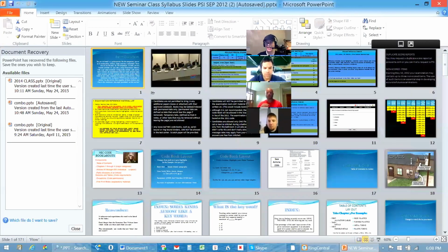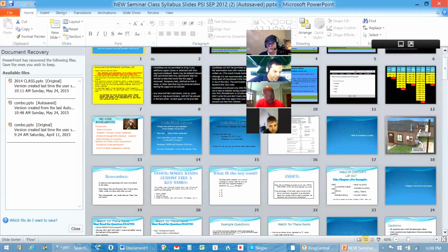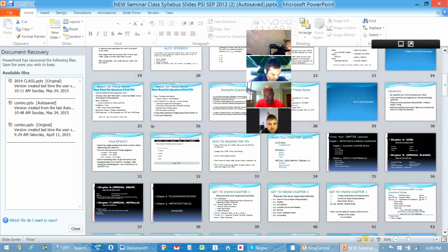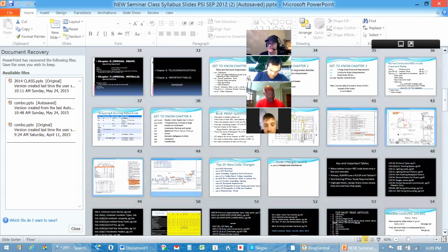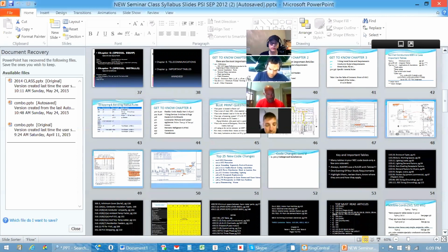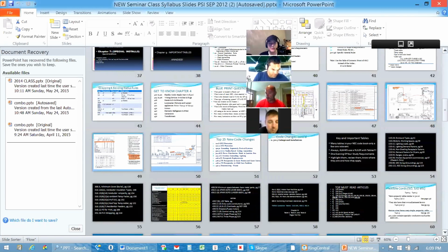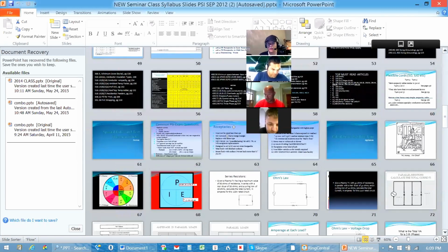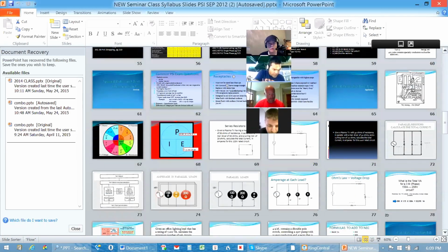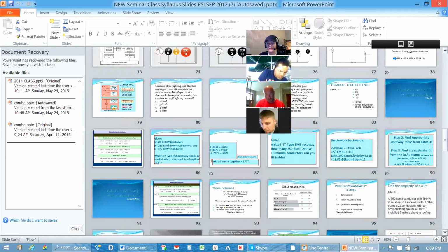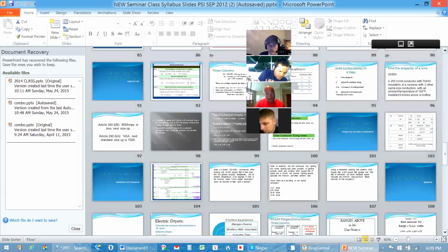The two most important tables that you'll deal with as far as the starting point goes is going to be table 220.12, which is on page 68 in the right-hand column. And I think we mentioned in class that dwelling units is one peculiar slot there, as well as hotels and motels that have provisions for permanent cooking. If you'll see right beside the word tenants there, and right beside dwelling units, both of them have that little letter A next to them. And that little letter A just denotes the fact that even though this is a lighting table, we're going to use it for both lighting and general purpose receptacle power for those two types of occupancies. So all your plugs in the living rooms, the bedrooms, the hallways, all that stuff is already included in that number you're looking at in the far right-hand column, which is 3 volt-amps per square foot. So it's really simple. We're just looking at 3 VA per calculated square foot.